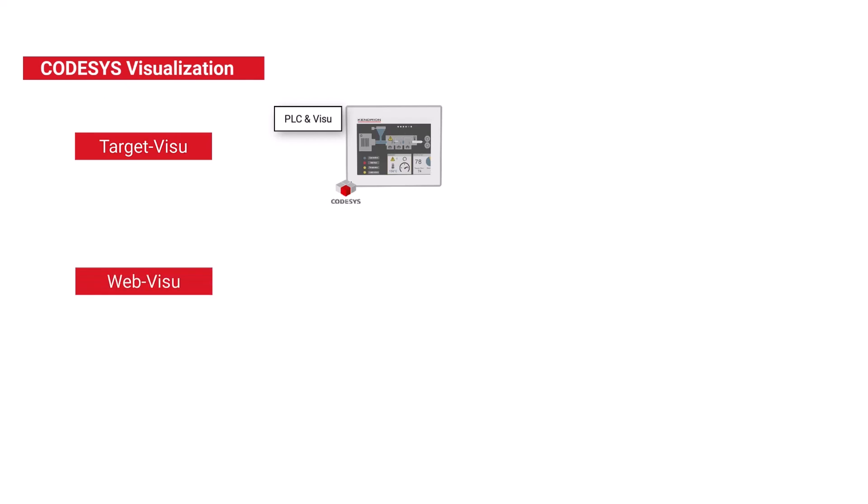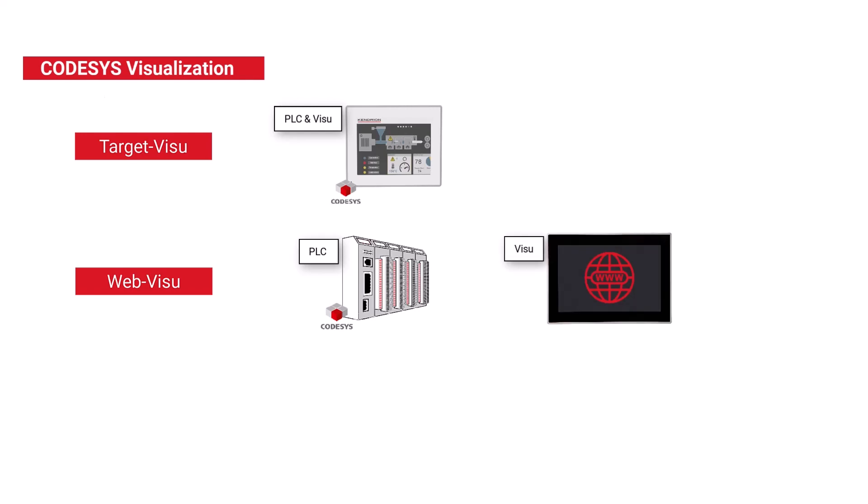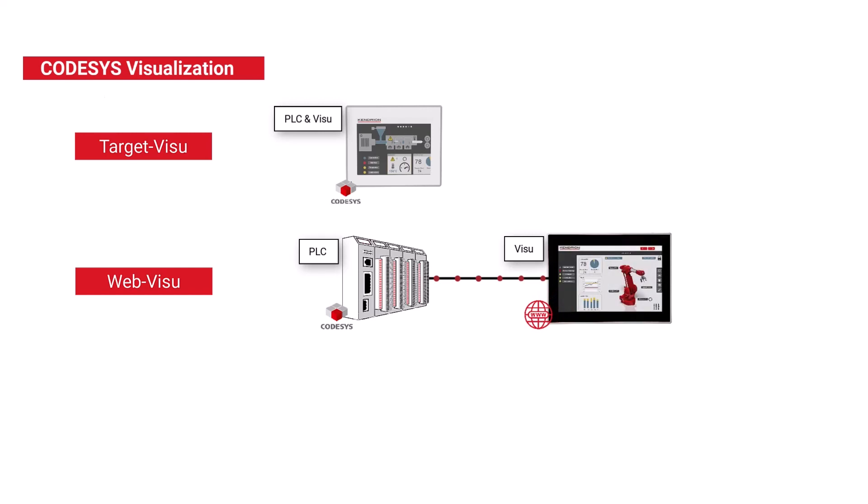Then there is a web visual. This one is also created within the CodeSys project, but the display takes place in an HTML-capable browser. The browser needs to be connected to the controller via LAN, so that the access to the data is possible from anywhere. Since the entire screen layout is handled by the controller, the PLC needs to do more computation compared to the target visual.